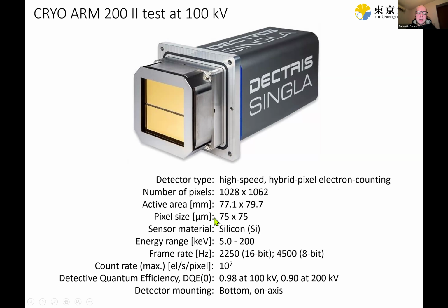Of course, the detector has a very large pixel to be able to do that. You see here 75 by 75 microns. That's 15, I think, I'm not sure if I can calculate it this hour, but 15 times larger than the typical direct detector now in electron microscopy. Also, the chip itself is much larger, so when it's mounted on the microscope, it's also a much larger area. And it's composed of two modules. You can see them here, and there is a gap between the modules.